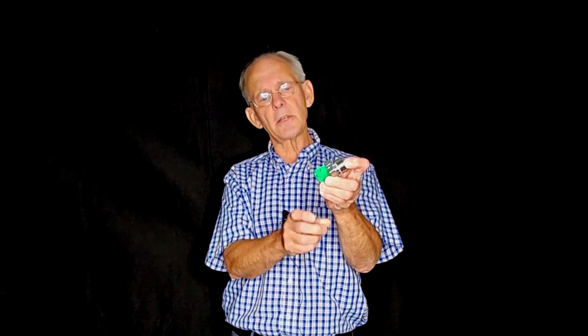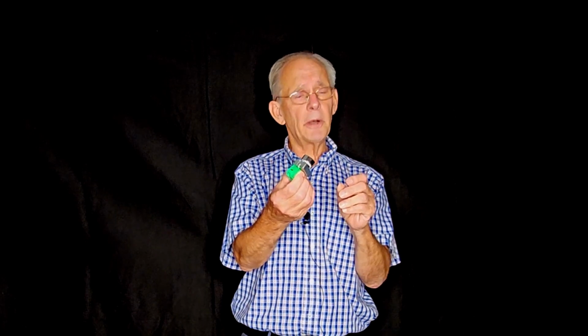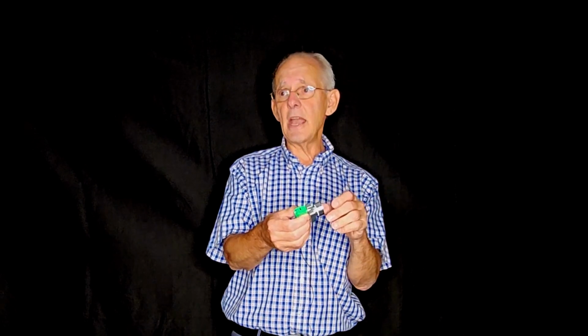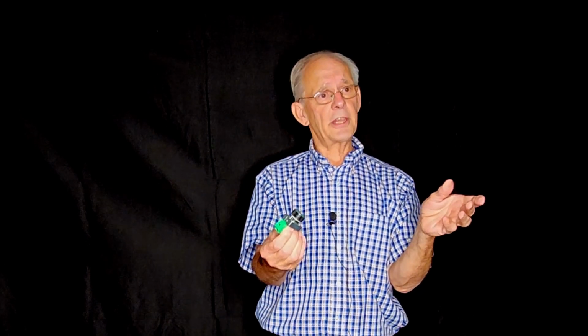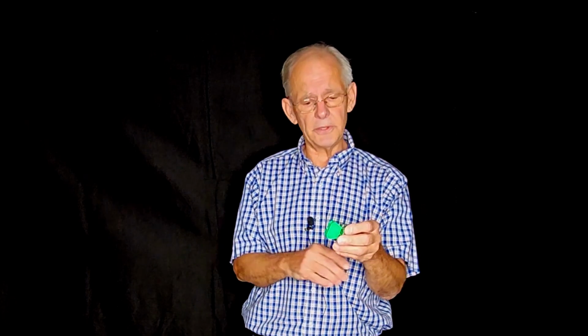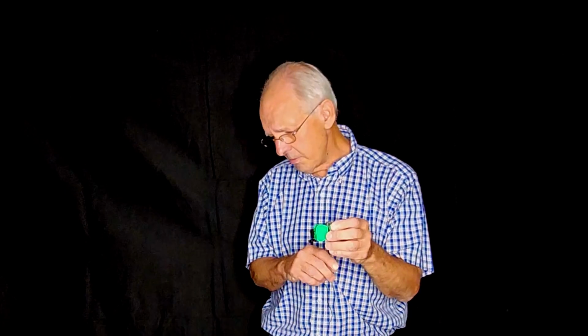You don't think of it as being a sensor, but push buttons are sensors also. And this is a mechanical push button, right? It works with a contact block. And in this style, which is a panel mount 22 millimeter, you can have multiple switch blocks on it. The green ones are normally open, and the red ones are normally closed, and you can stack them up and have a lot of different circuits switched at the same time. And we don't do that much anymore, because normally now we just take the signal from a single push button and go to a PLC input, and then the outputs from the PLC can switch a lot of different things.